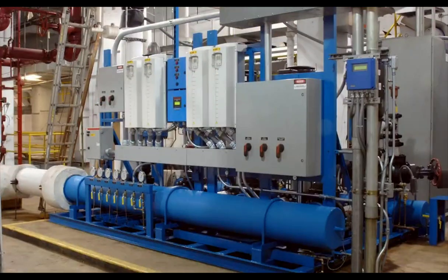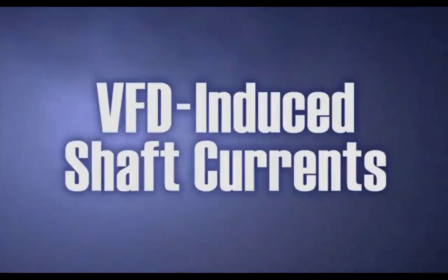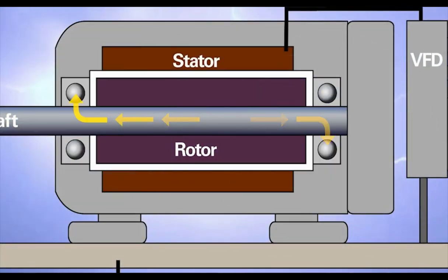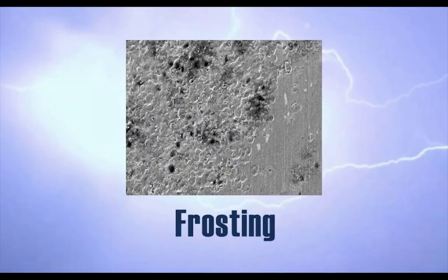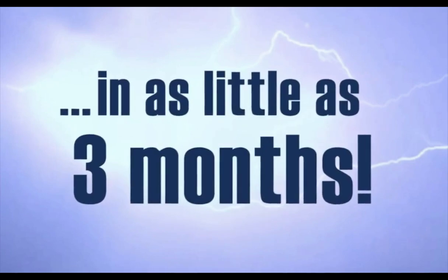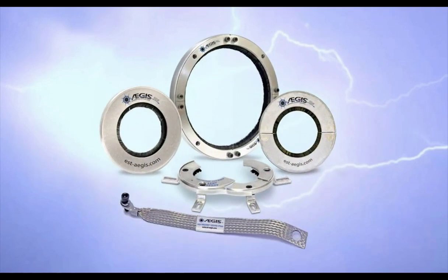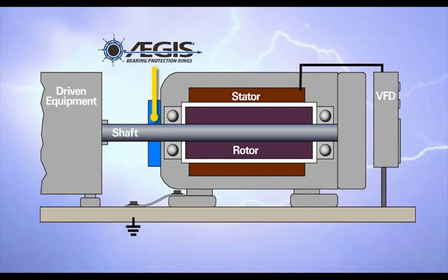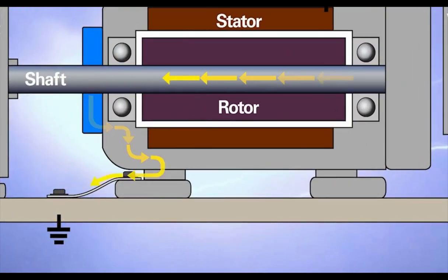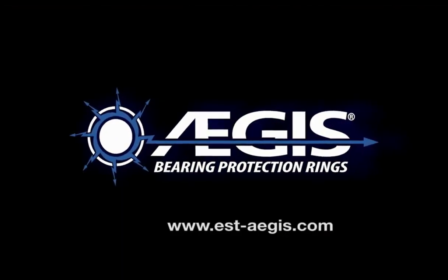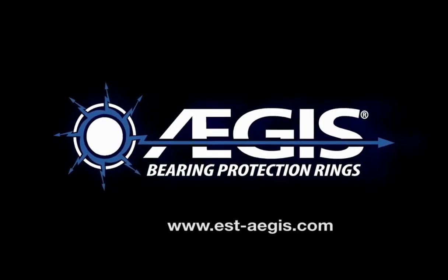VFDs can save 30% or more in energy costs. But VFDs can also damage motor bearings. Without shaft grounding, VFD-induced voltages can discharge through motor bearings causing damage such as pitting, frosting, and fluting, and unplanned motor failure in as little as three months. Revolutionary new AEGIS bearing protection rings provide proven long-term protection against VFD-induced bearing damage. By channeling harmful shaft currents away from bearings and safely to ground, AEGIS rings ensure that motors last for the L-10 life of their bearings. To protect motors from bearing damage, prevent process downtime, and secure VFD energy savings, specify AEGIS rings.